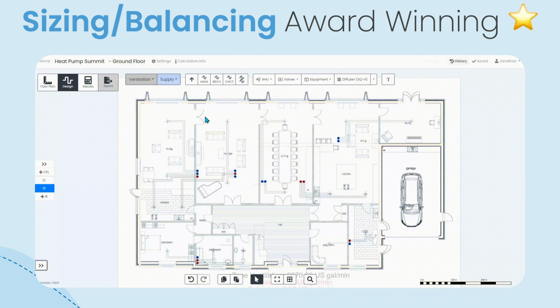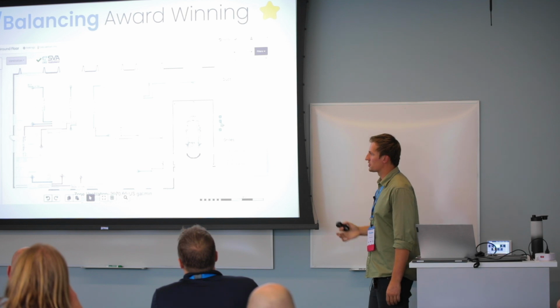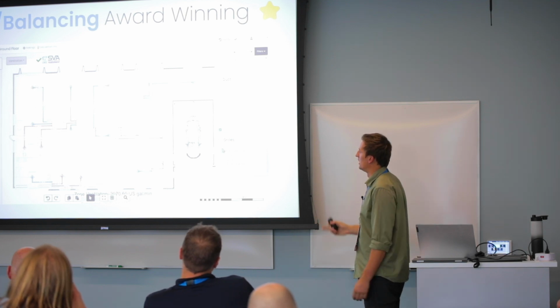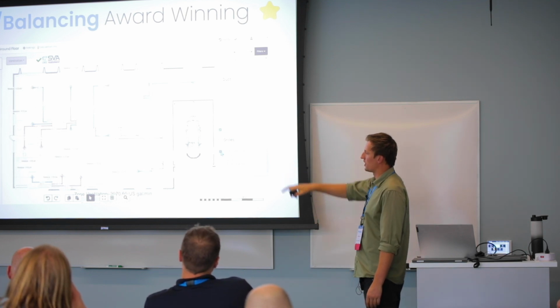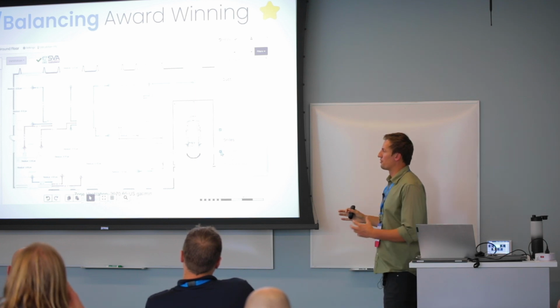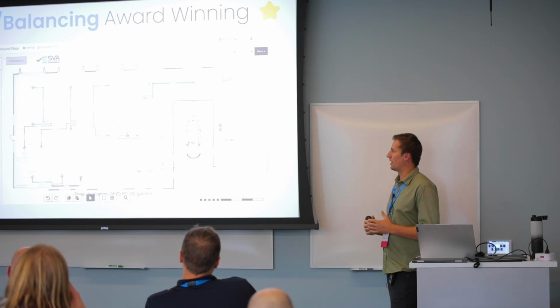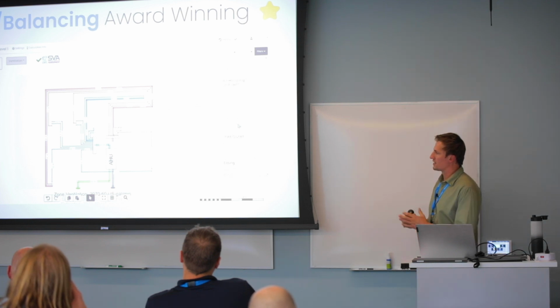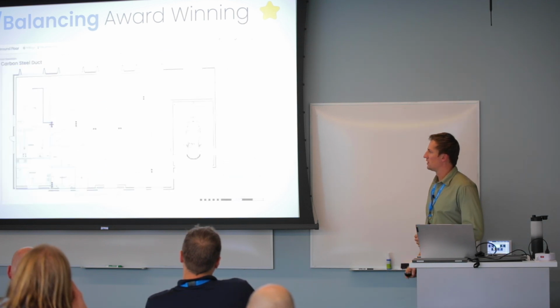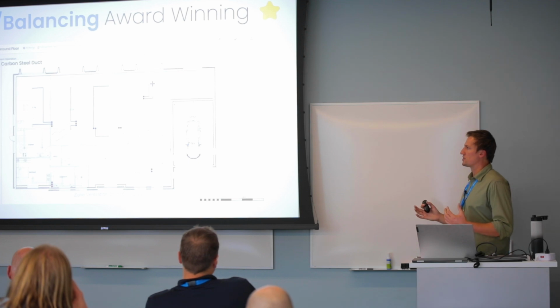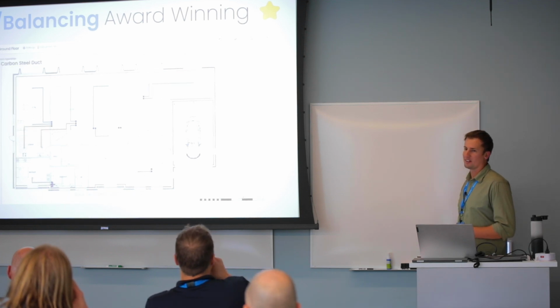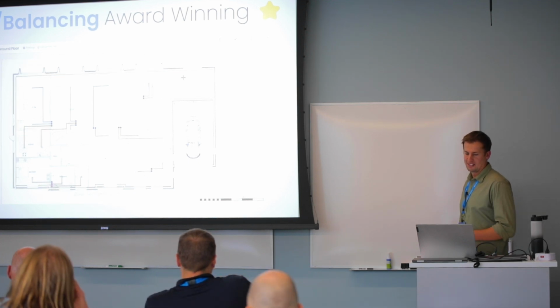As this goes through again, sketching out the proposed ductwork layout, as they go around and drop on the grills and the diffusers, it's assigning the flow rate to make sure the building gets the heat. When it sizes everything, you can see velocities, pressures, flow rates, the sizing. Most importantly, what you want to see is that all the pressures are equal. Through what we call dampers, balancing devices, it's making sure that as it branches off, everywhere's getting equal pressure. This can be done on site, but it's much harder to do accurately because you're running around every room, making sure it happens.